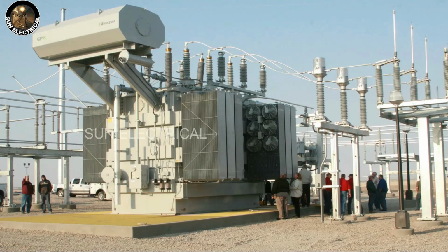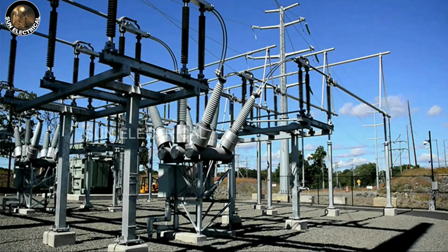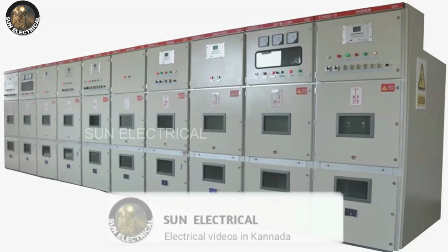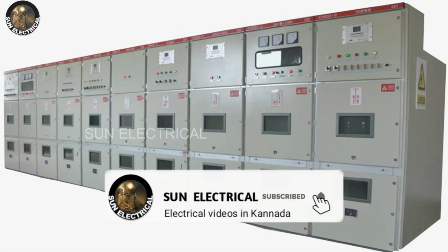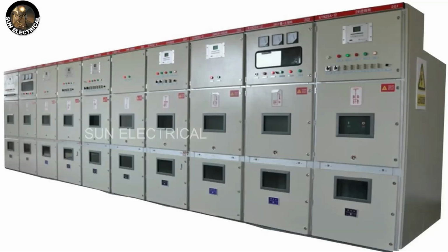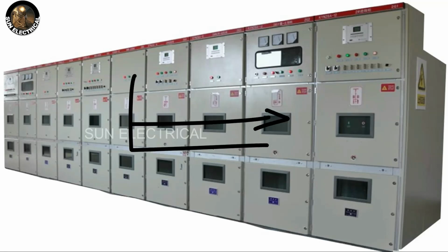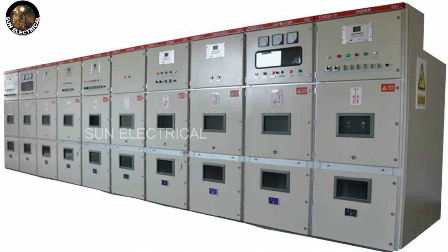Using DC supply instead of AC supply in substations and industries also gives some extra facilities. When protective devices operate with DC supply, they take much less reaction time than when they operate with AC supply. AC supply sometimes fluctuates, sometimes 230, 229, 228, but DC supply is constant, a continuous supply because of direct current.